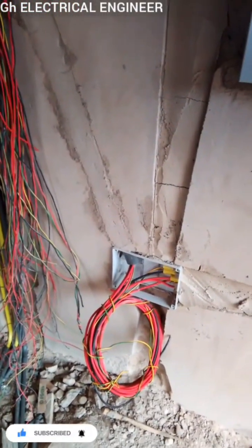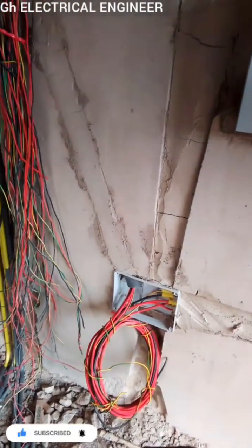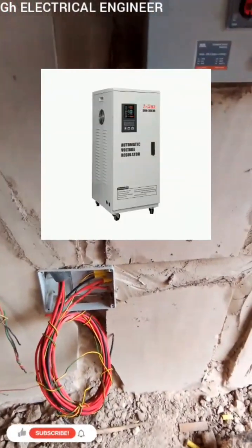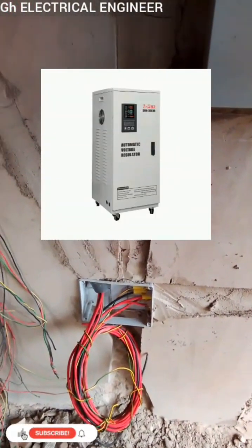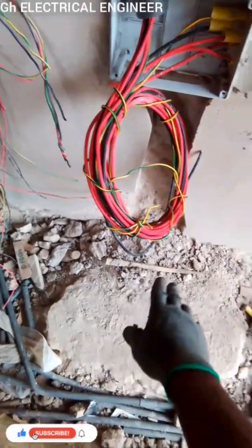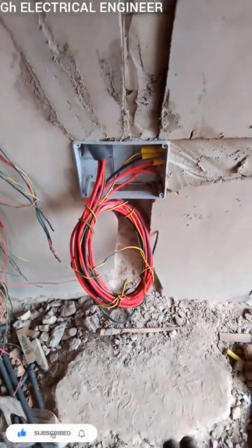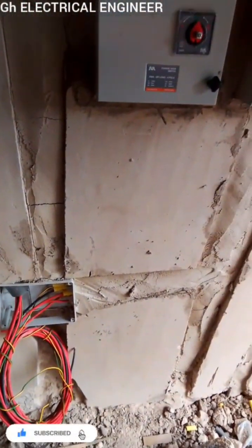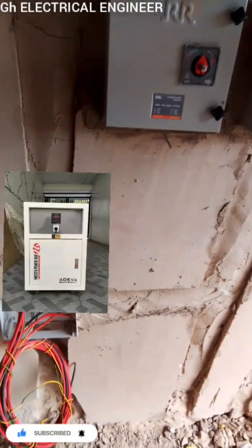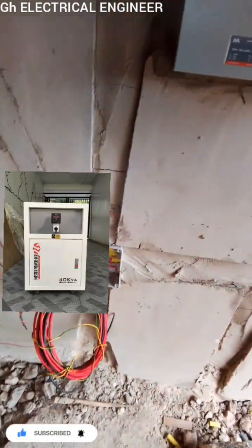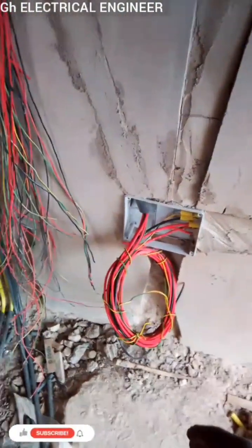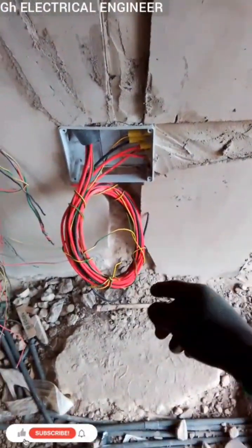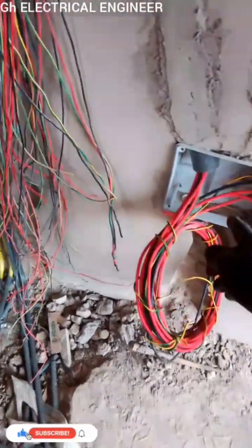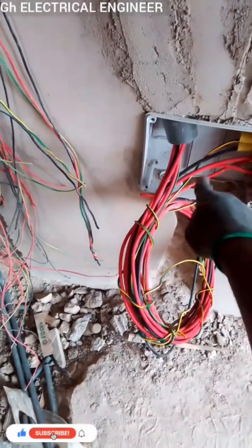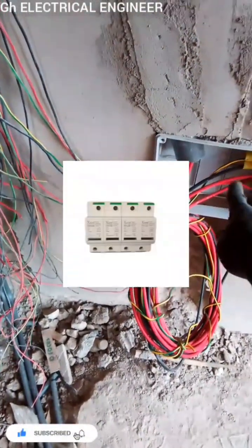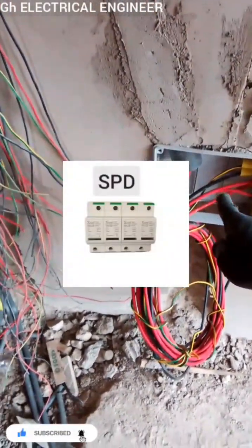We are going to invest in an AVR, an automatic voltage regulator, somewhere around here, like a 30 to 40 kVA, 3-phase AVR. Then from the AVR, when the power goes through, it comes here, where we are going to set up an SPD, a surge protective device.